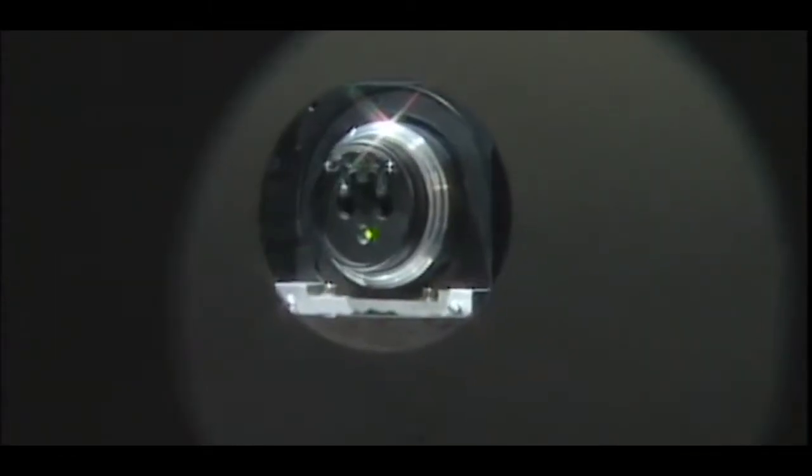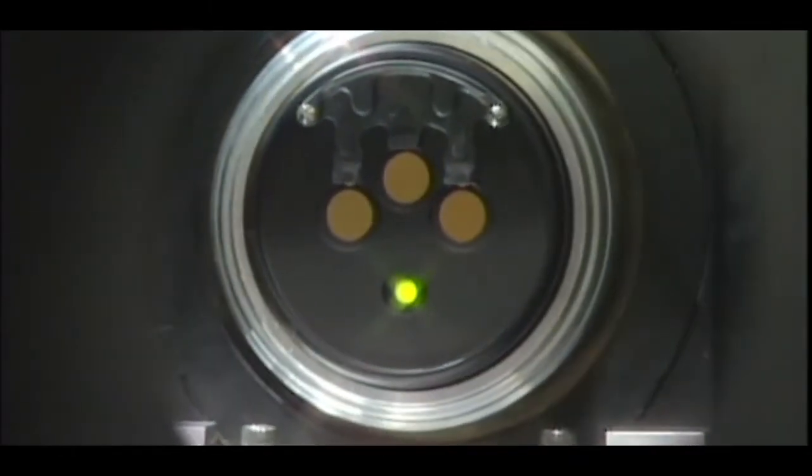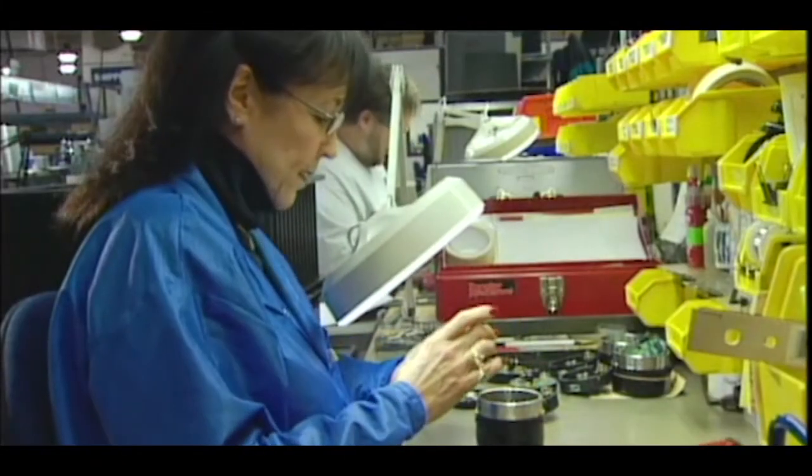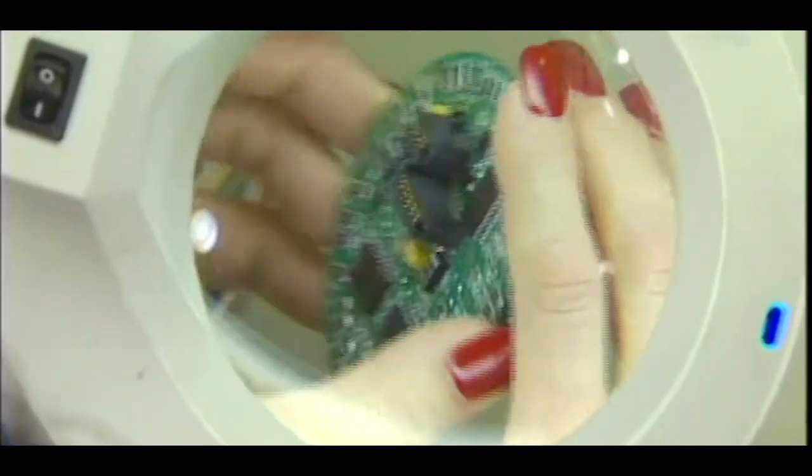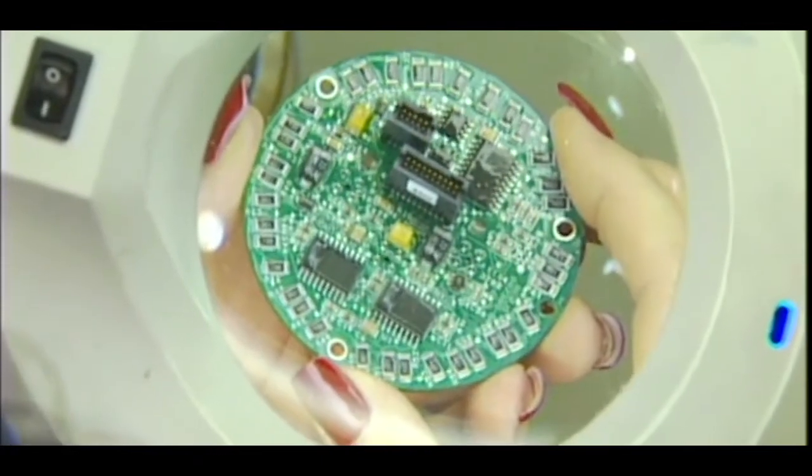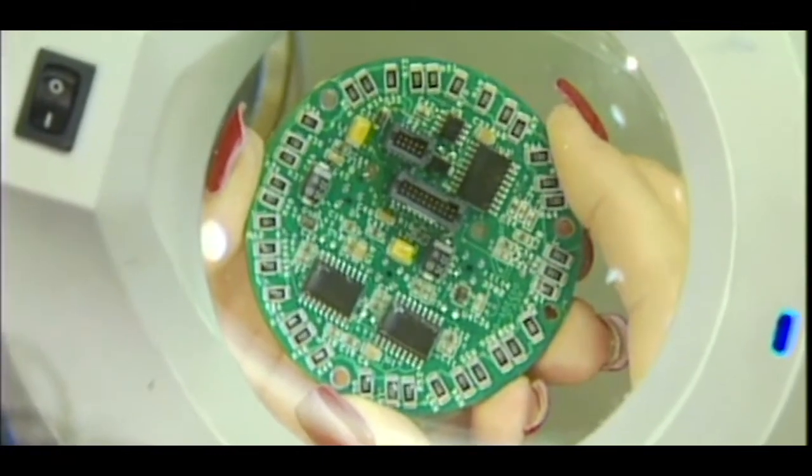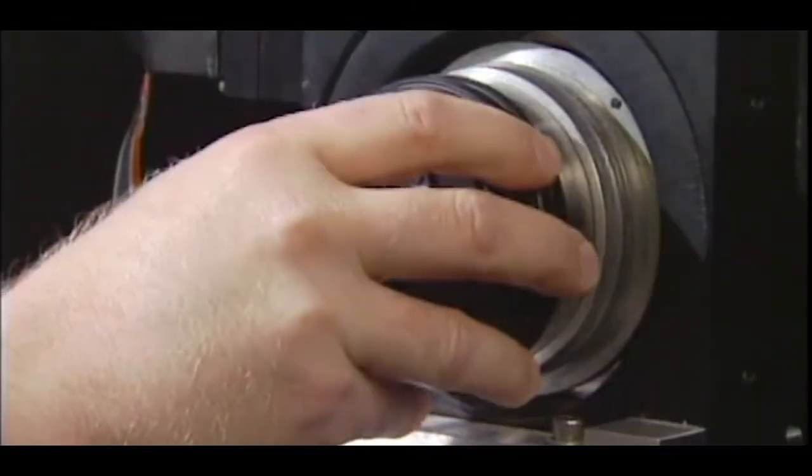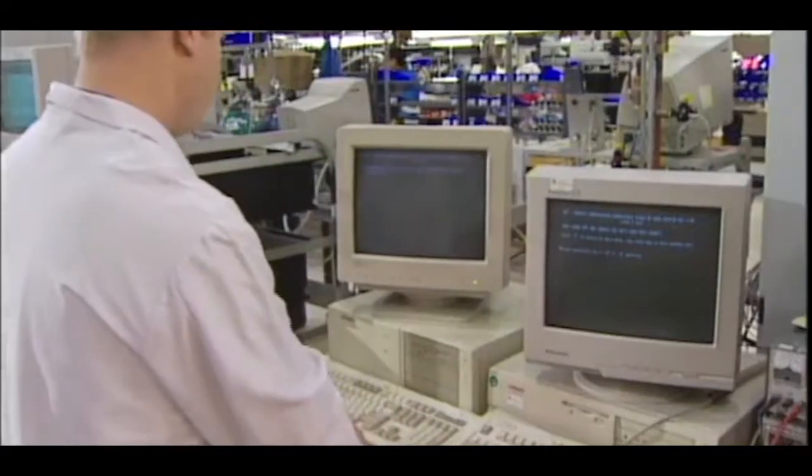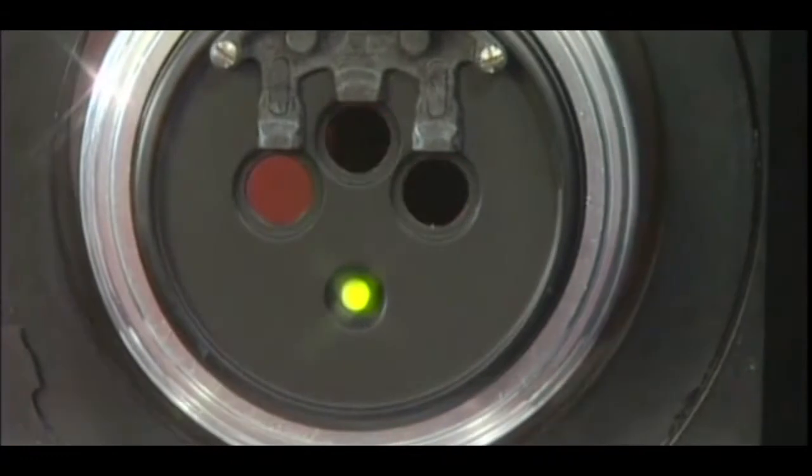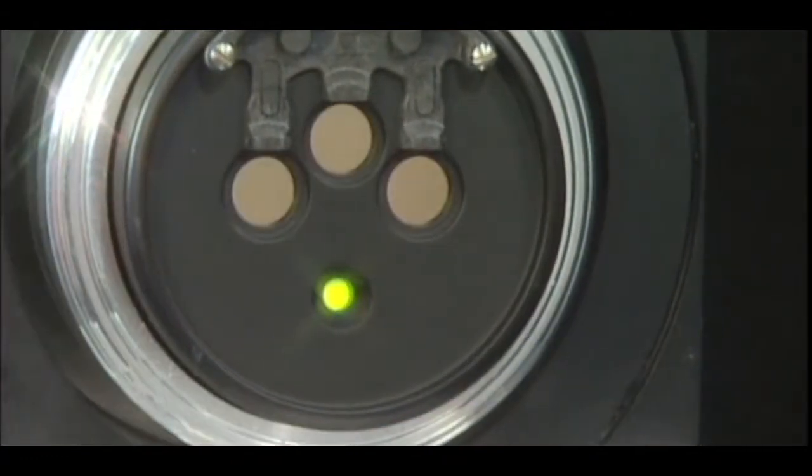Protector utilizes three regions of the infrared spectrum to gather data within its field of view. This data is continually analyzed using patented advanced signal processing algorithms supported by an embedded 32-bit microprocessor. Wavelength, flicker, intensity, and time domain are just a few of the discriminators used to evaluate what the detector sees.